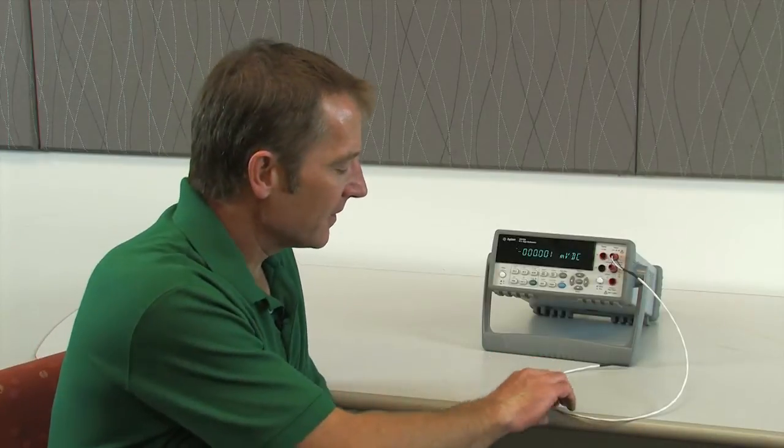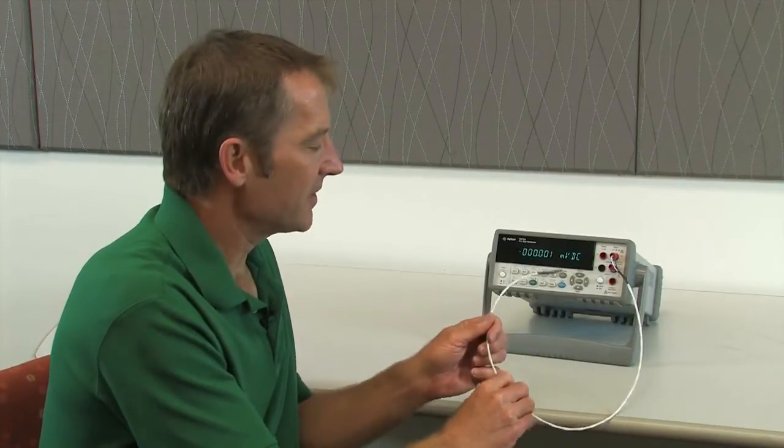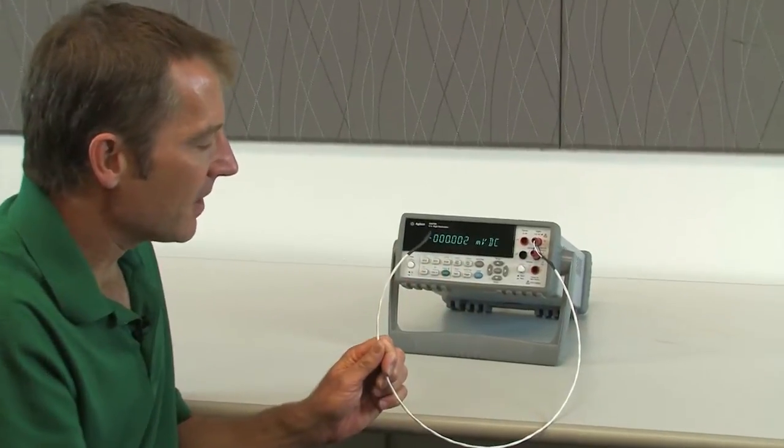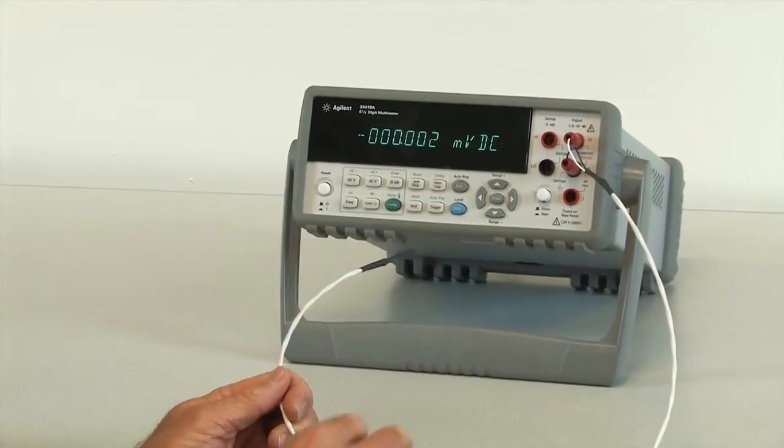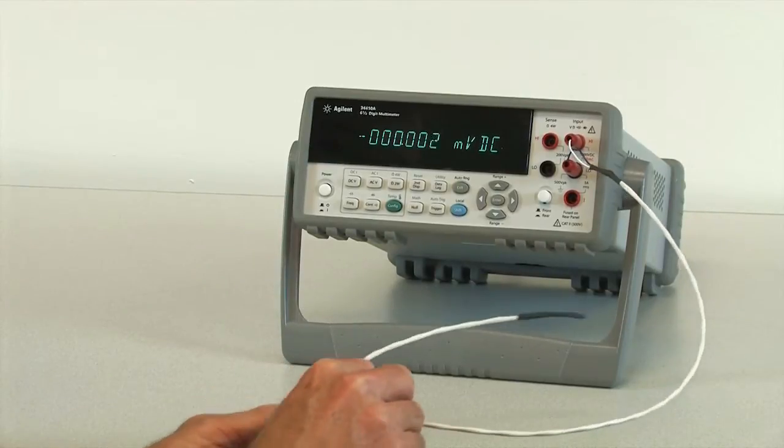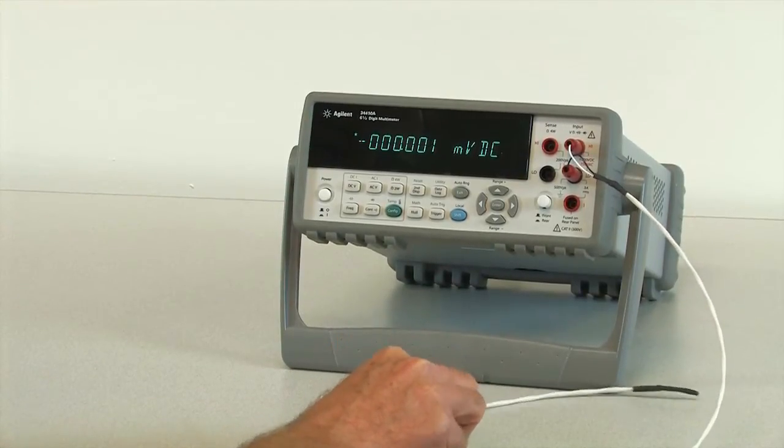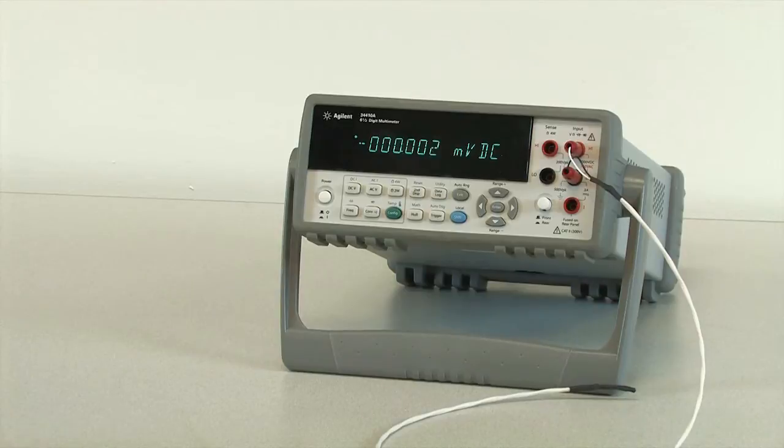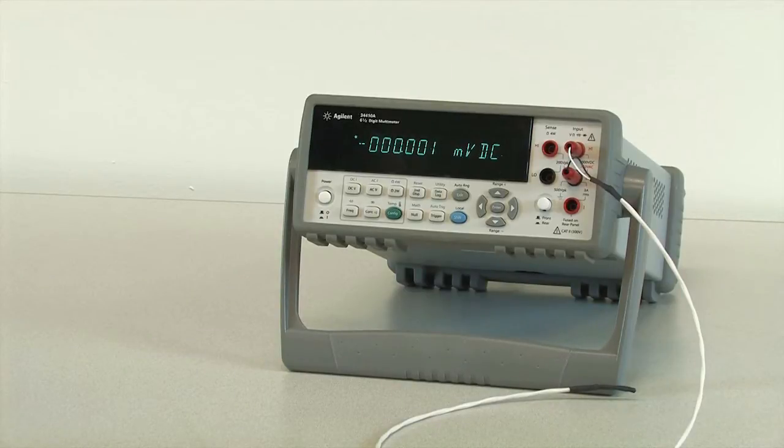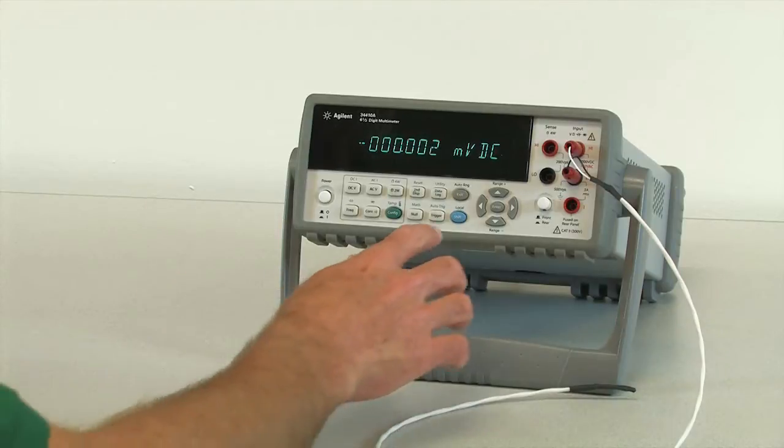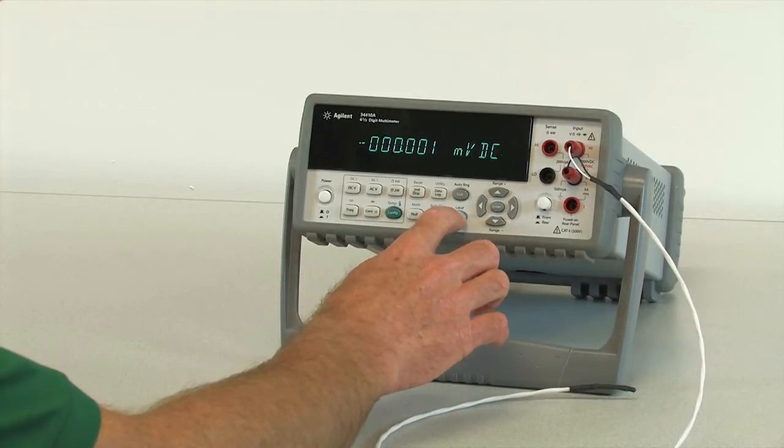Here's our completed temperature probe. As you can see, we have the thermistor on one end of our shielded twisted pair cable, and some banana plugs on the other end. We've connected it to our 34410A multimeter, and now we can set up the 34410A for temperature measurements. It has many different built-in algorithms for measuring temperature.